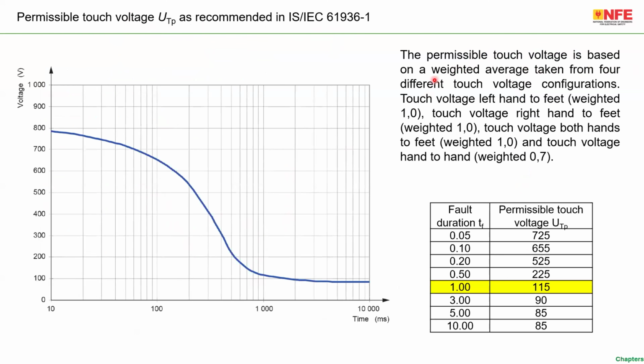The permissible touch voltage is based on a weighted average taken from 4 different touch voltage configurations. Anyway, this is from the previous standard. I don't explain it here. For example, if we are talking about the tripping time of the circuit breaker during a high voltage fault, the maximum allowed touch voltage is 115 volt. If we are talking about a disconnection time of 3 seconds, then the maximum allowed touch voltage is 90 volt from this particular graph. This is the recommended figure which is there in the standard IEC 61936 part 1.